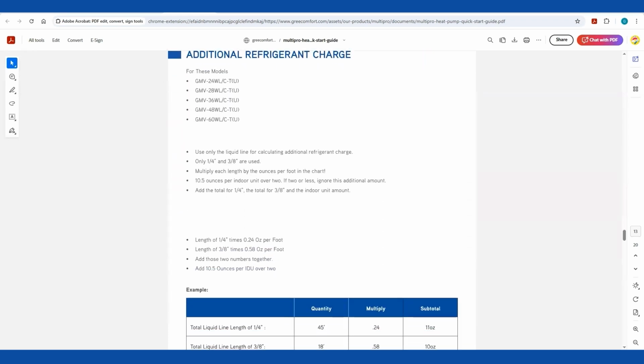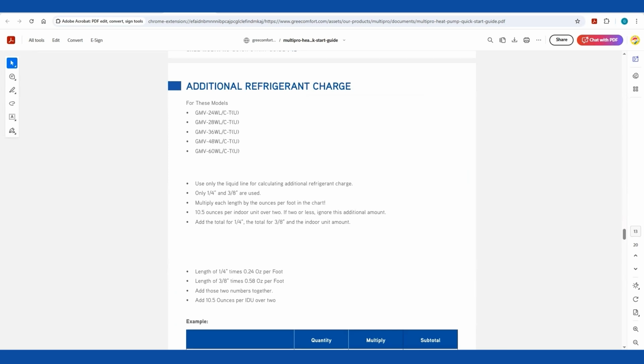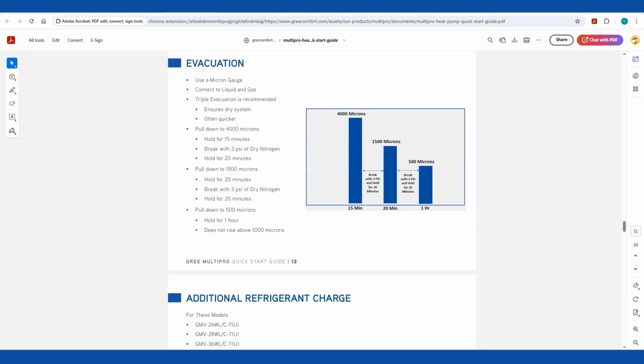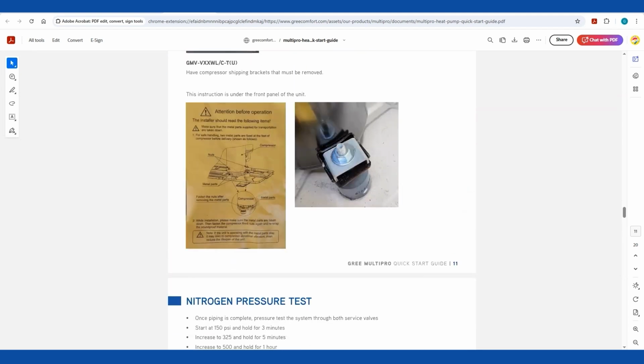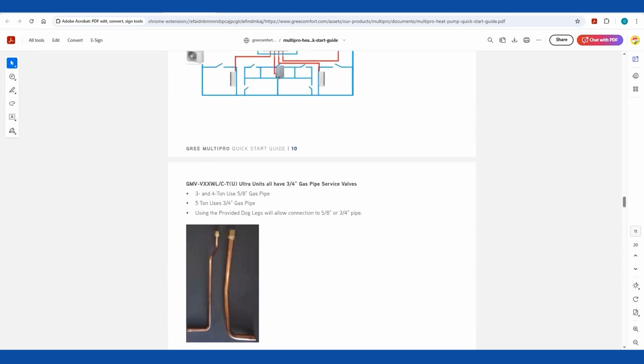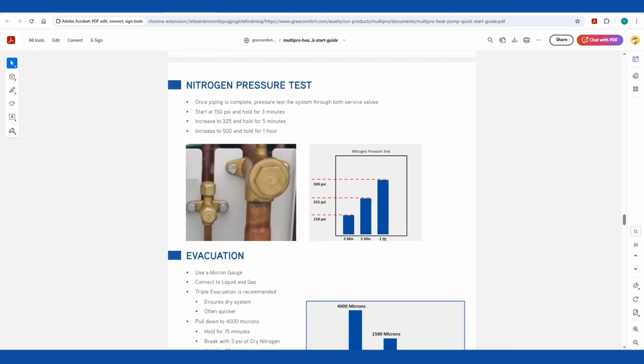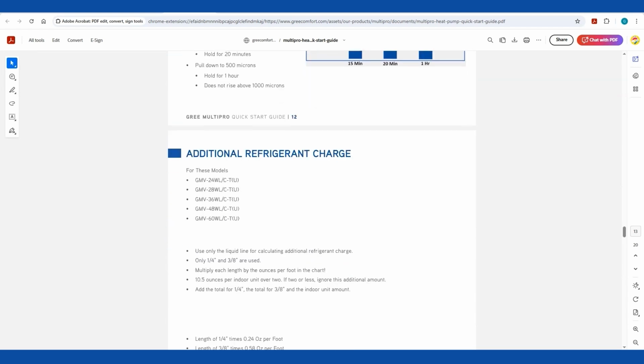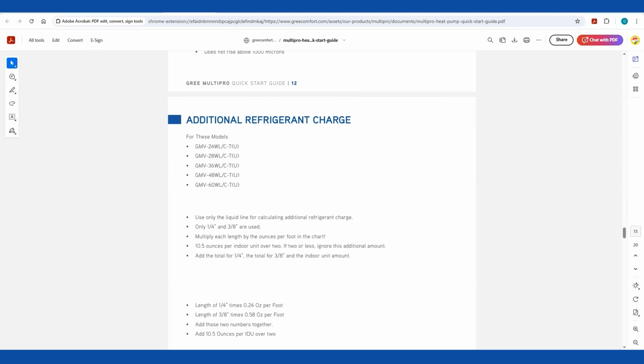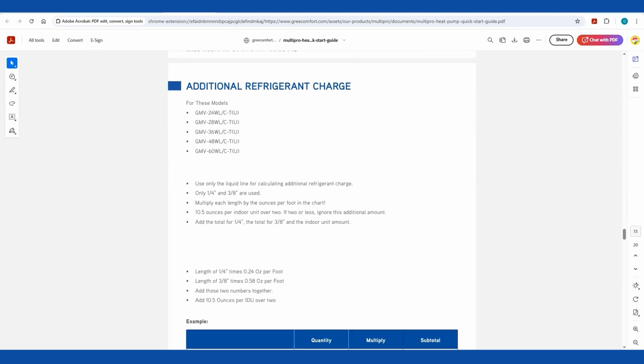An additional charge. So on the standard models, the ones that don't have the 2 V's in it, the Ultras have the 2 V's. I'm going to go back real quick and show you that. You'll see V in that model. That's Ultra. Here, these are all standard, no double V's. You can manually calculate that charge. Use only the liquid line for calculating an additional charge. Only 1/4 inch and 3/8 are used.